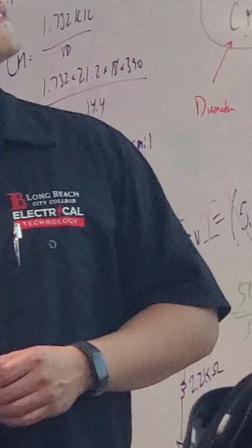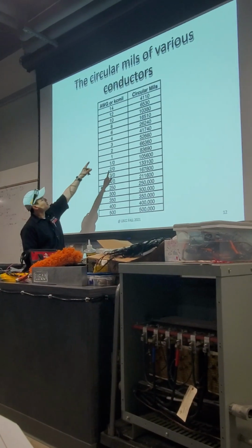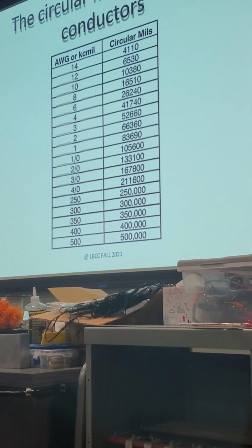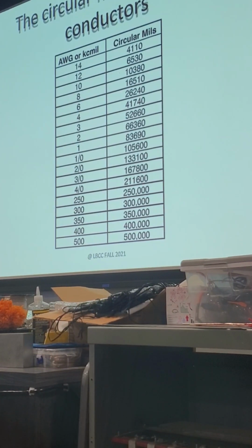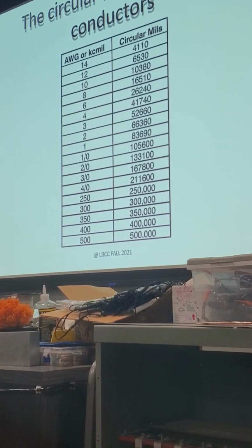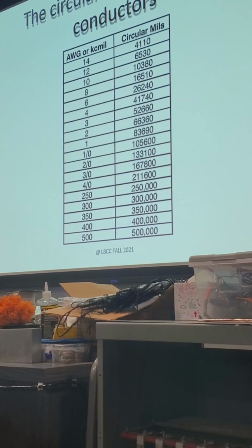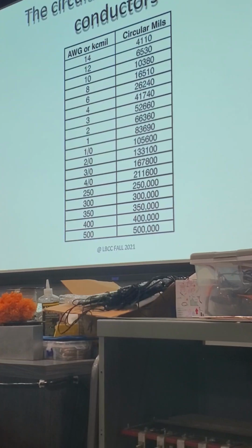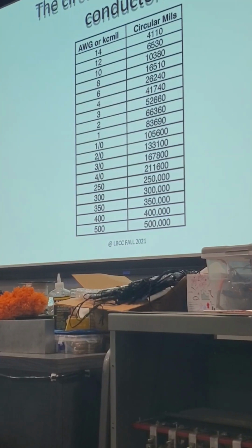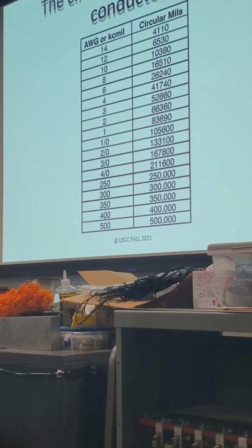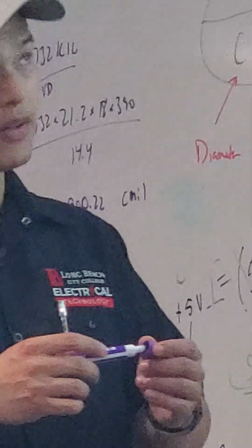Sean? 6 gauge conductor? 6 gauge, 6 AWG. But number 8's cheaper, right? And we want to cut corners. So depending on your customer, unfortunately the customer is always right, but definitely Sean is exactly right. NEC is the minimum installation recommendation for the protection of personnel and property. Absolutely, I would agree with you that even though it is over-spec, let's say, our number 6 AWG, which is good for 26,240, is going to be our size of choice.